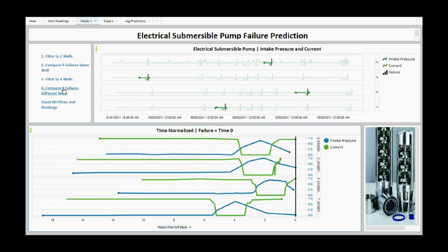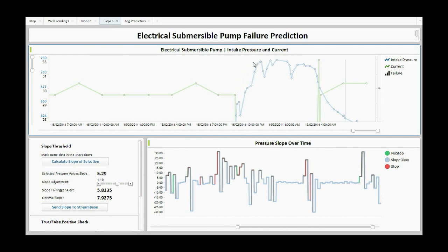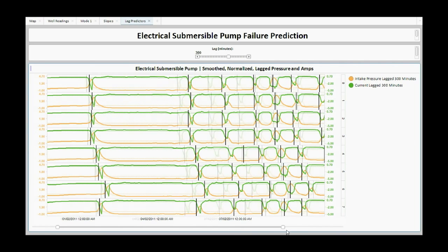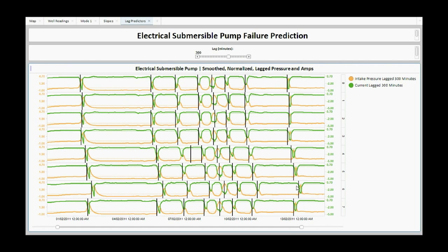Some leading indicators for pump failure are a large increase in motor temperature causing an electrical short, and unusual changes in pressure forcing the pump to shut down. Those models can then either generate a condition score for a piece of equipment assembly or indicate a possible imminent failure. The thresholds and other model parameters are used to configure the appropriate modules in the accelerator and turn that knowledge into detection logic to be applied to the streaming data.